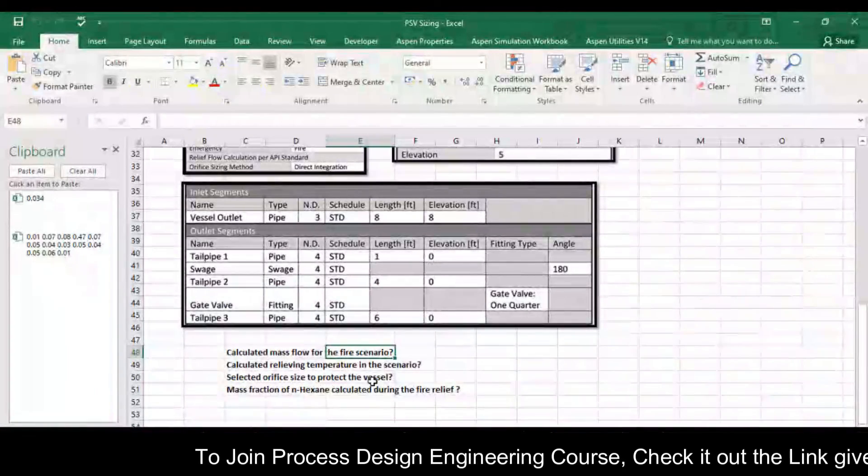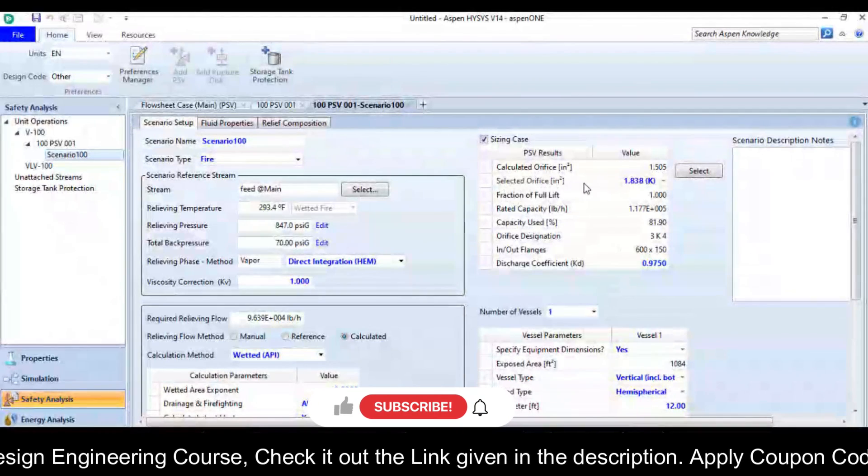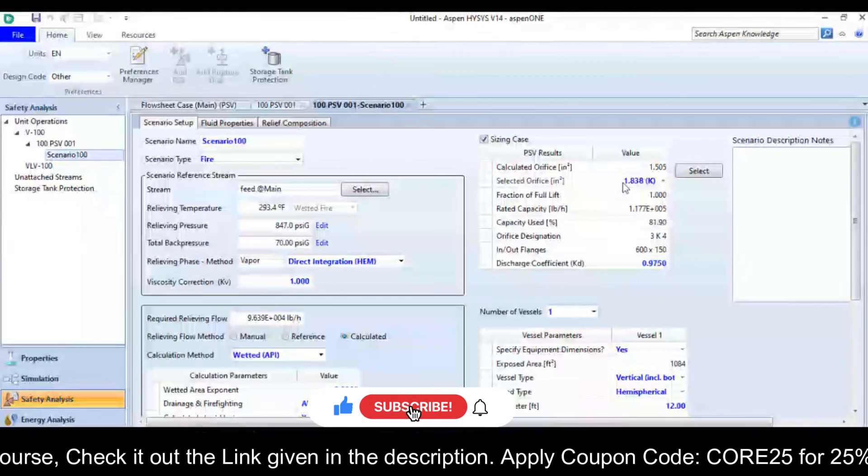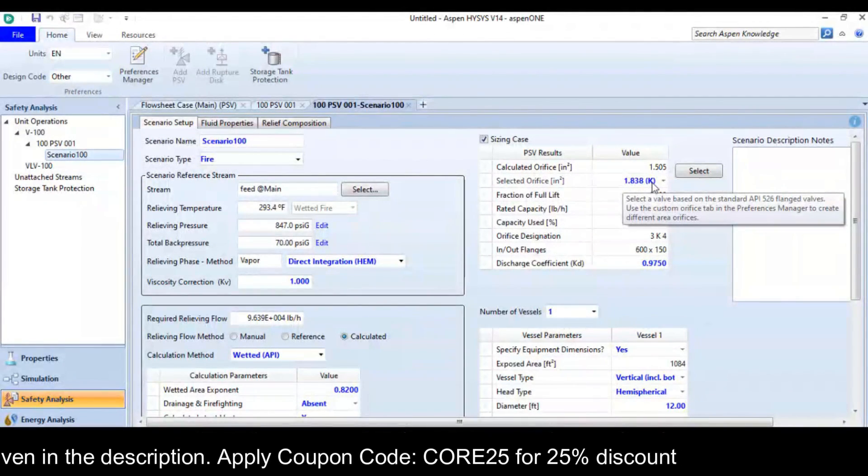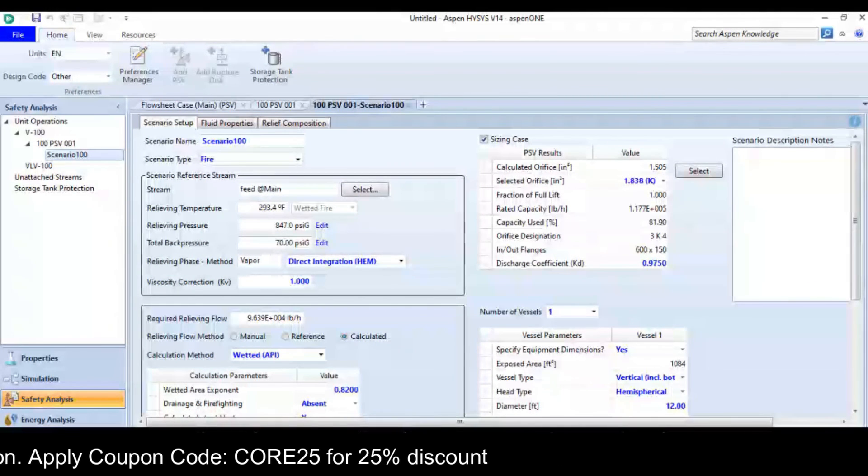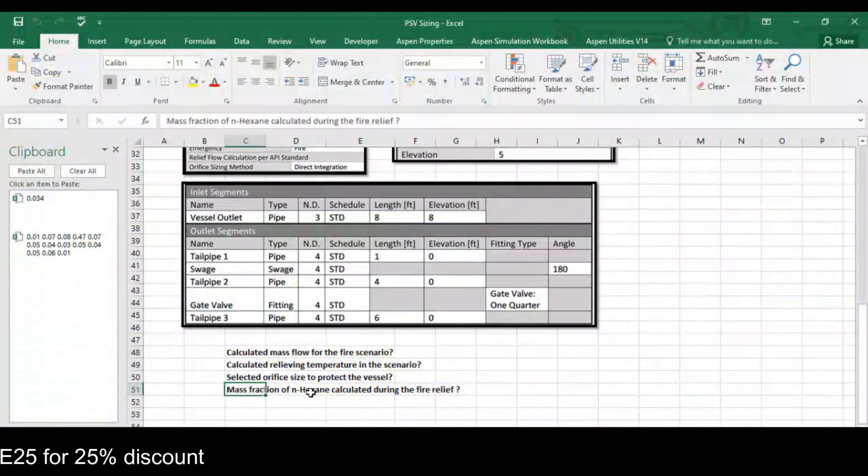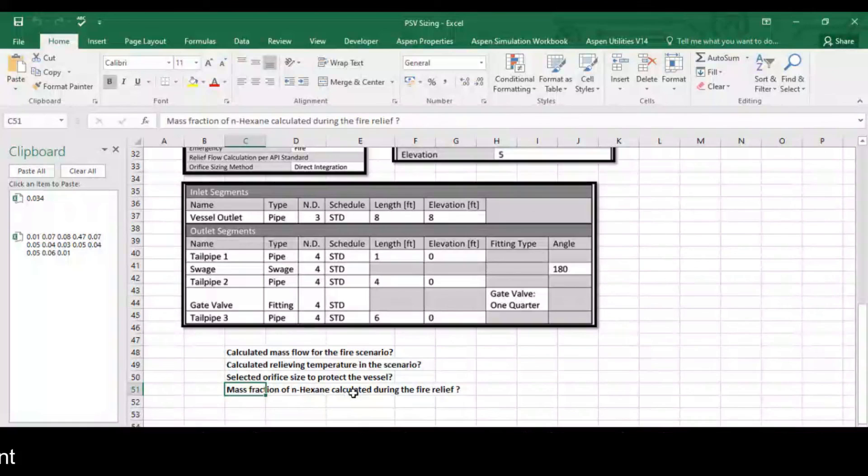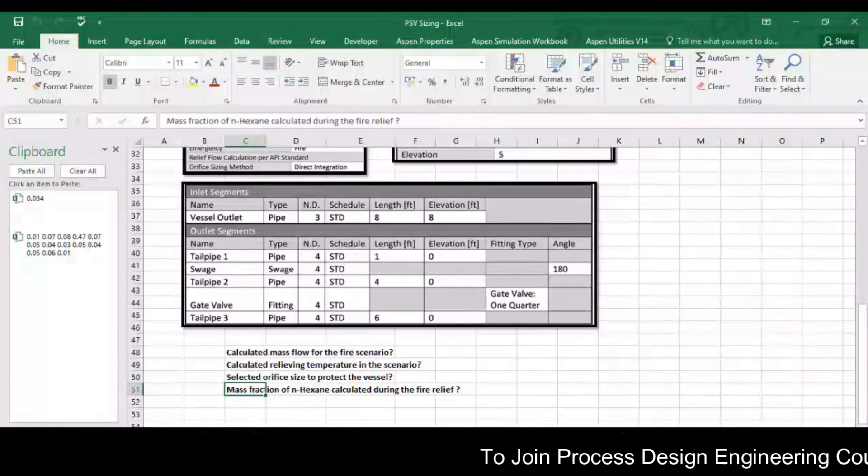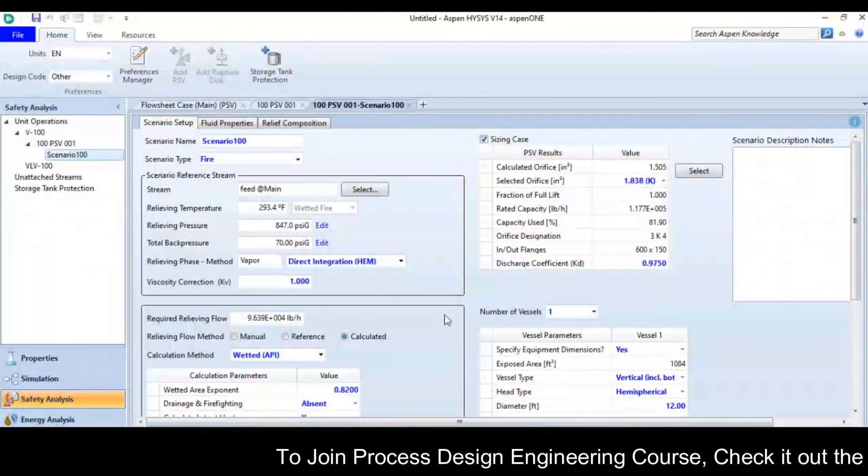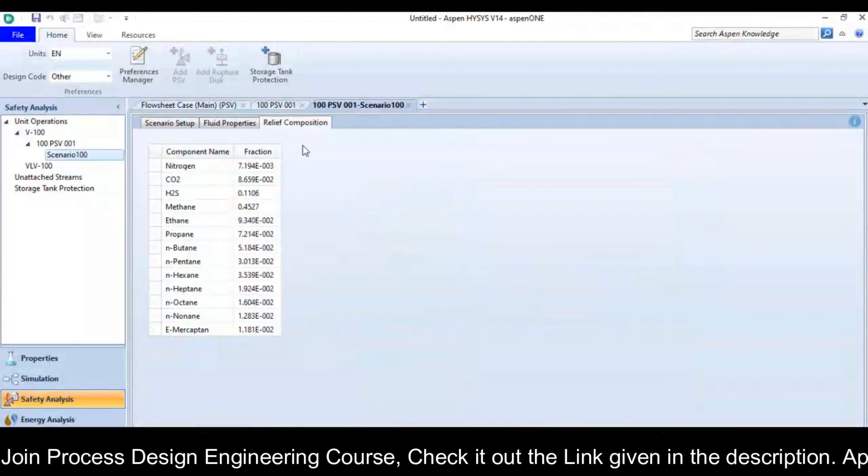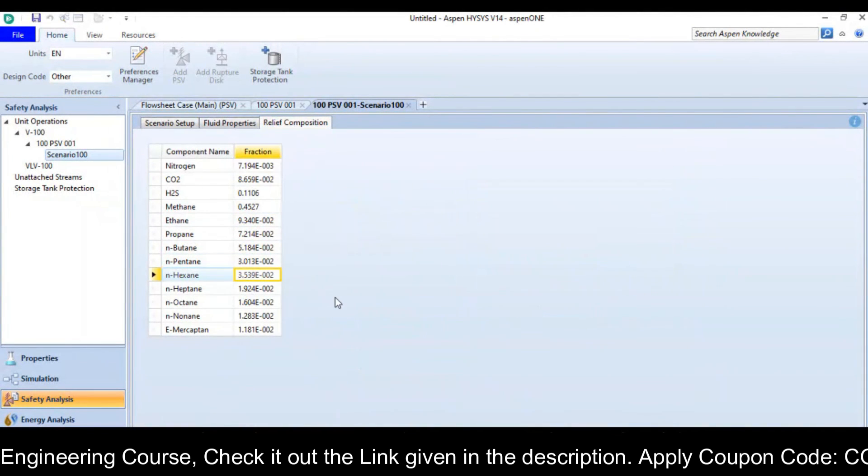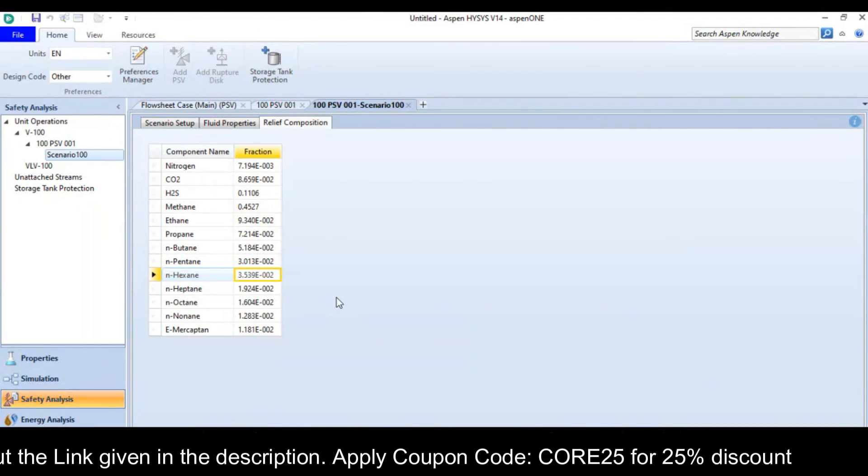Selected orifice size to protect the vessel. So this is your selected orifice size 1.838, the designation is K. And the last thing, the mass fraction of n-hexane calculated during the fire relief. So you can go to relief composition and you can see there n-hexane is 3.5 exponential minus 2.